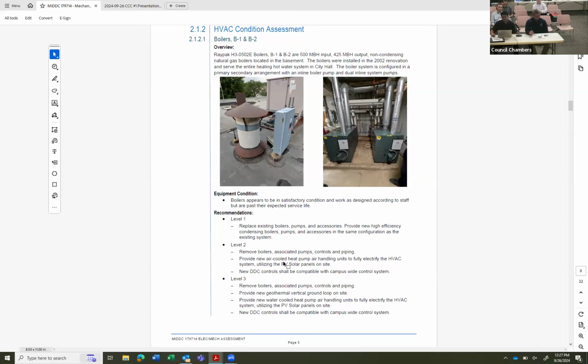And moving on to level two, we'd also be removing the boilers, but we'd be removing the entirety of the boiler system, which should include all the existing piping and much of the ductwork. Some of it can probably be salvaged for the new system, but basically we'd be replacing the boilers with variable refrigerant systems. So those systems include essentially outdoor condensing units that would be tied via refrigerant to indoor fan coils, air handlers, smaller air handlers, and potentially individual cassette units, ceiling cassette units in individual offices.